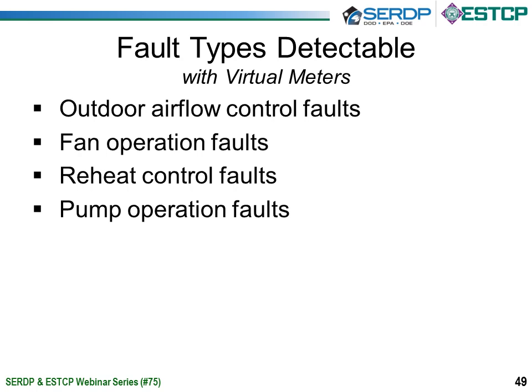So that's the technology. And now I want to turn to an application, which is detection of faults in the equipment and systems using these virtual meters. There are 4 categories of faults that can be detected using this technology. Outdoor airflow control faults, for example, a stuck outdoor air damper, the minimum position for ventilation only of the outdoor air damper being incorrect, and related faults. There's also fan operation faults, which I'll show you an example of, reheat control faults, and pump operation faults. And each of these represents a set of faults.